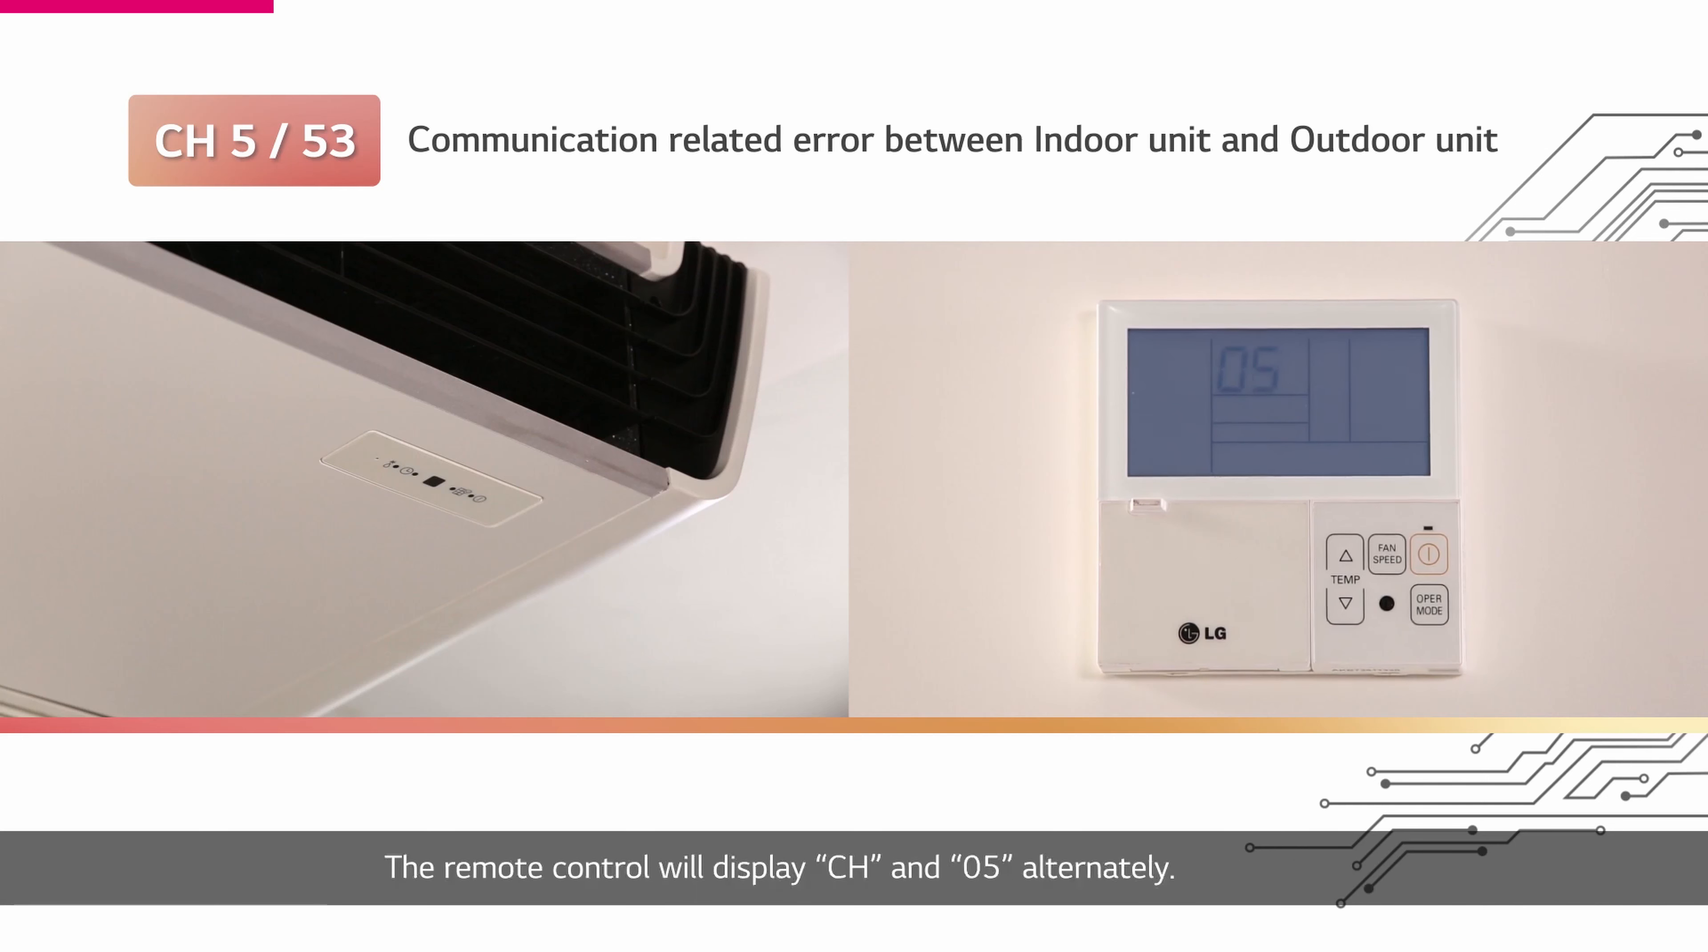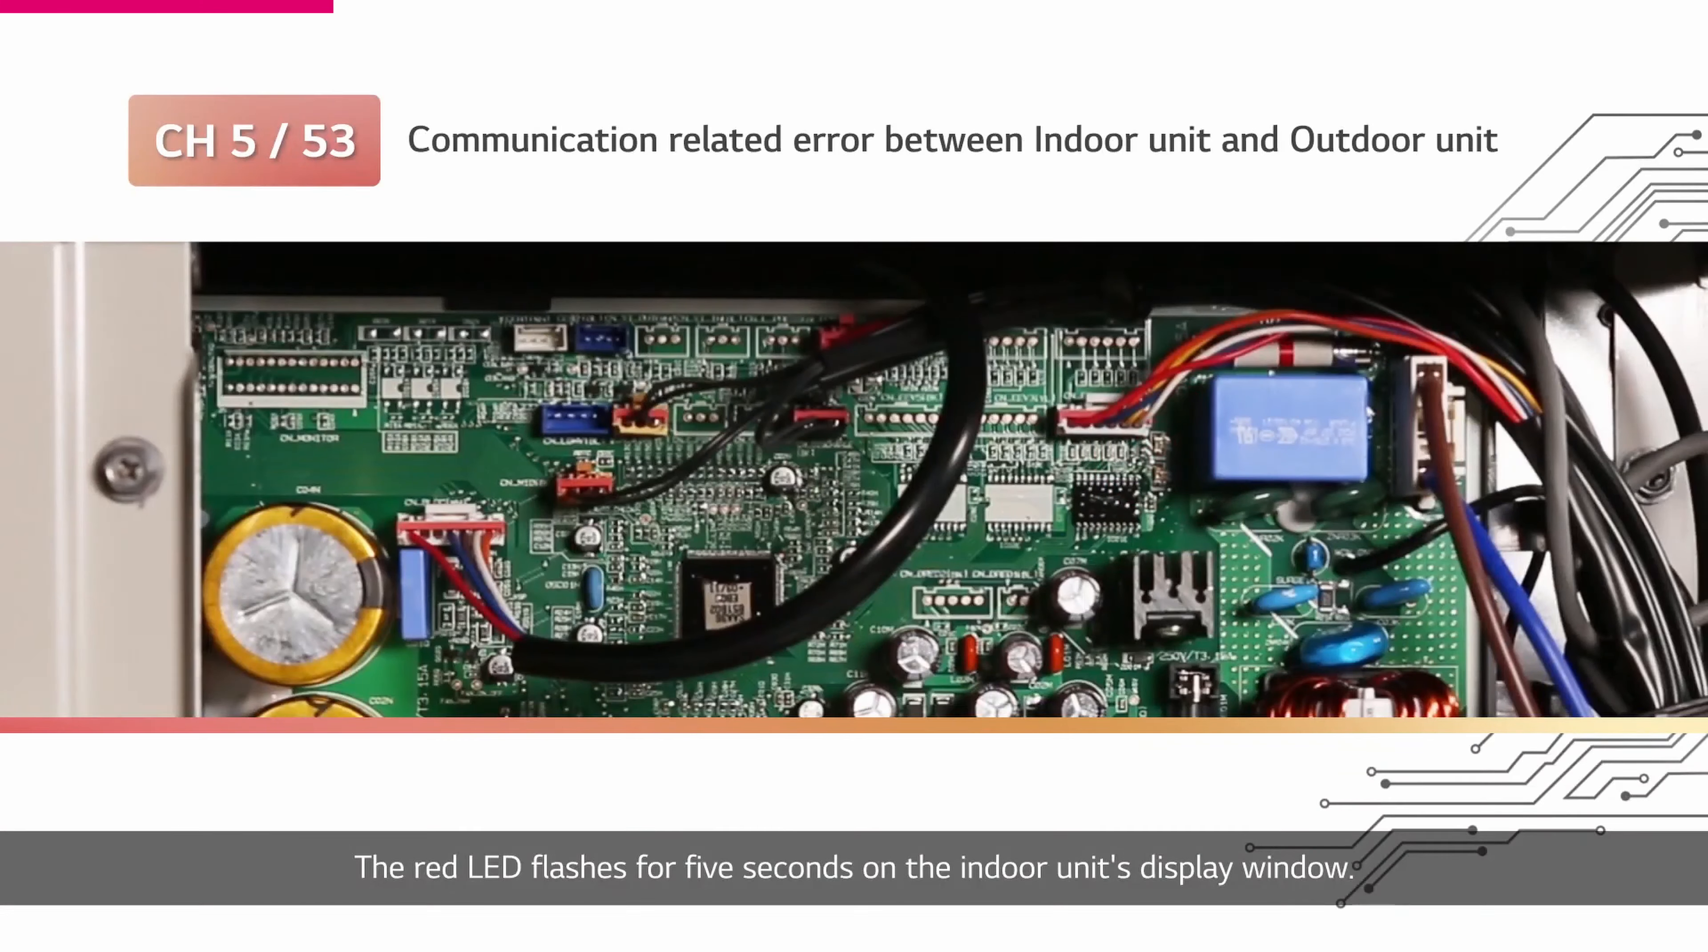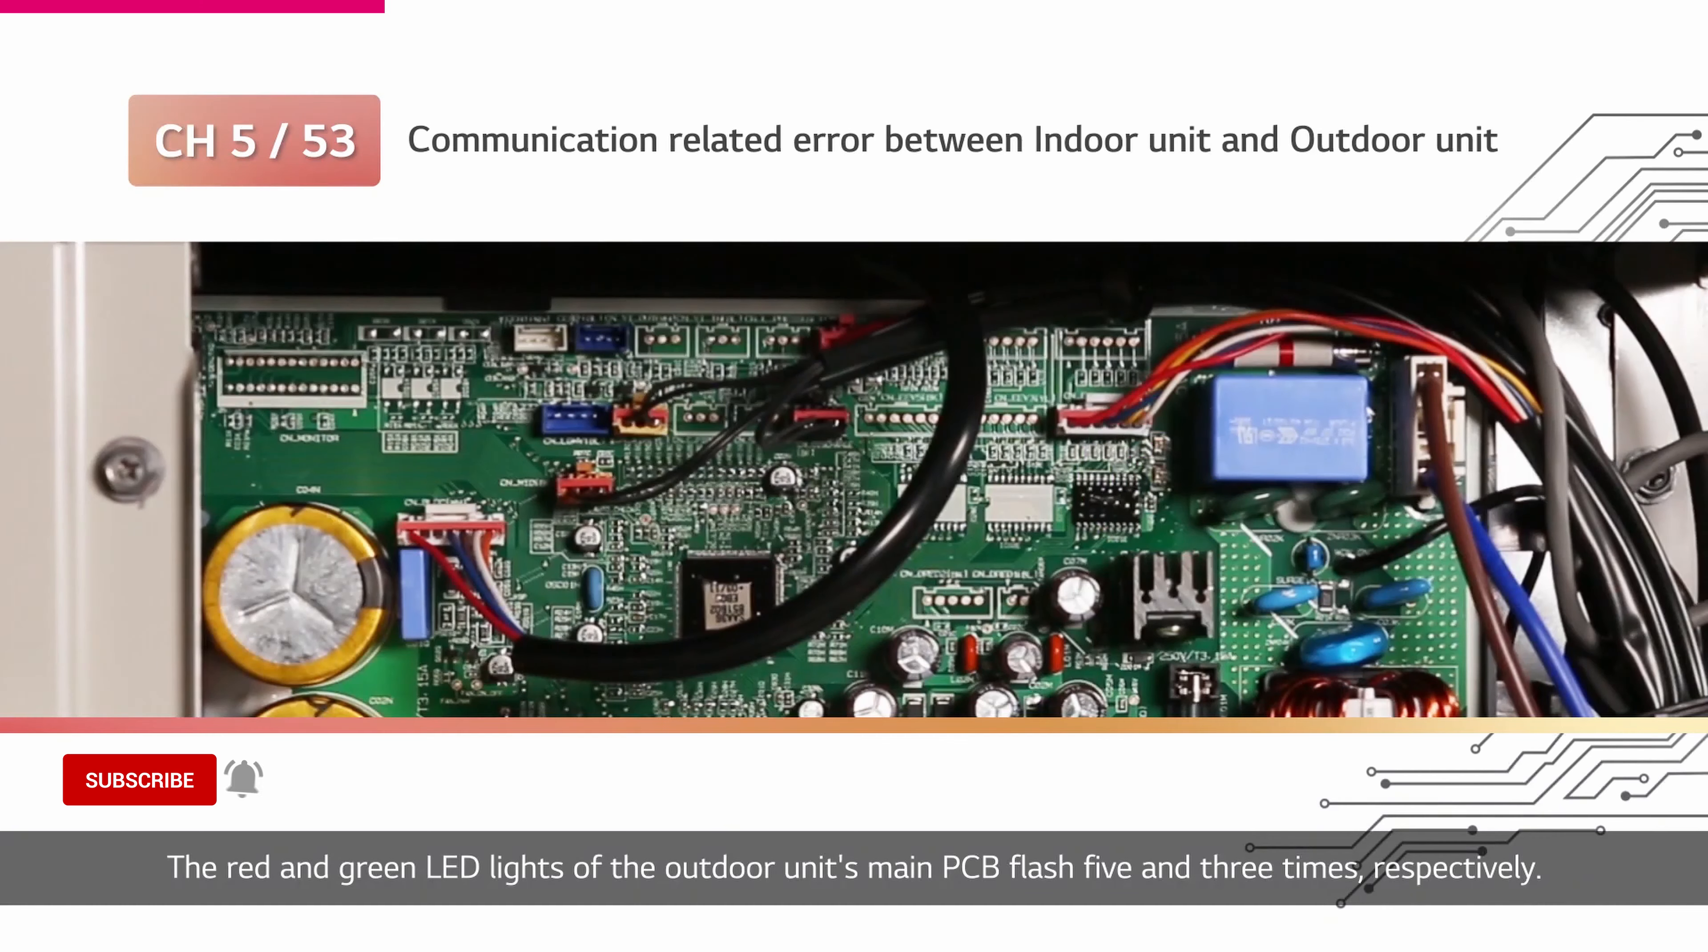The remote control will display CH and 05 alternately. The red LED flashes for 5 seconds on the indoor unit's display window. The red and green LED lights of the outdoor unit's main PCB flash 5 and 3 times respectively.